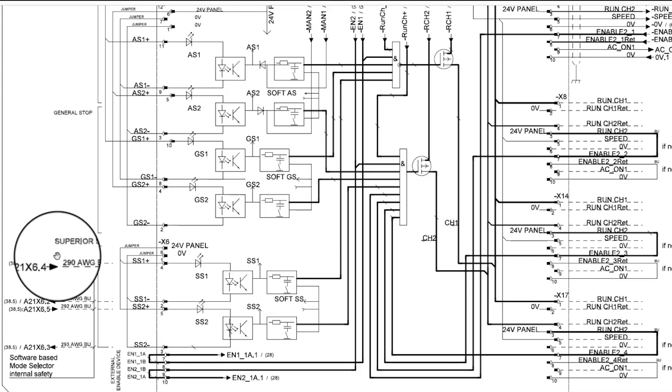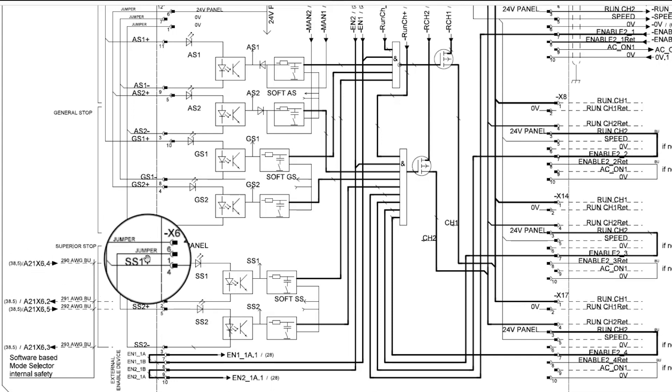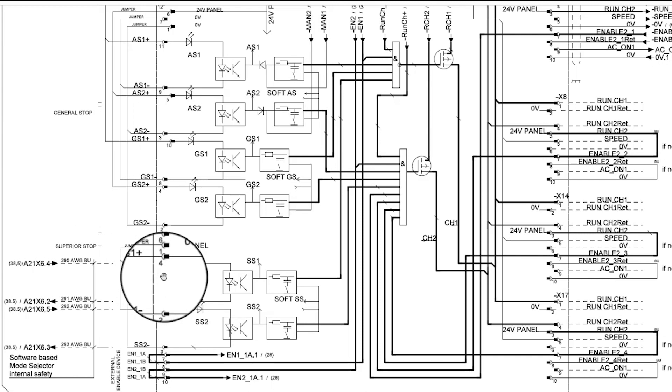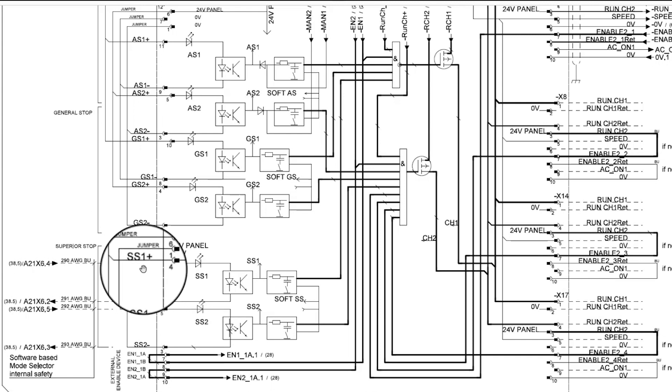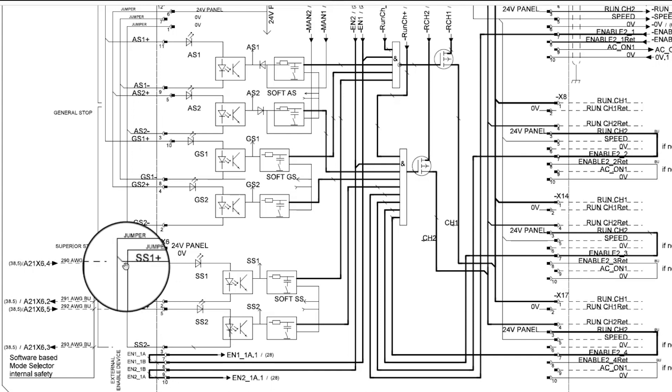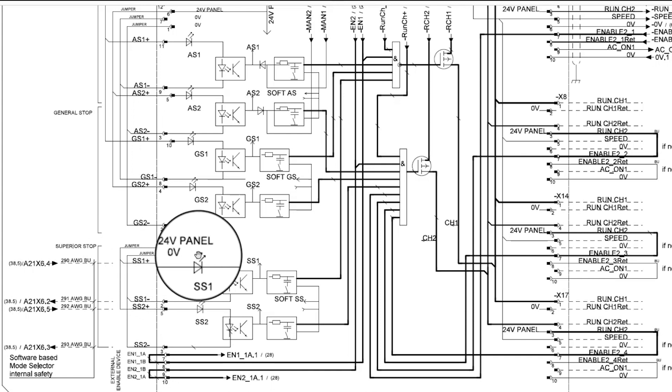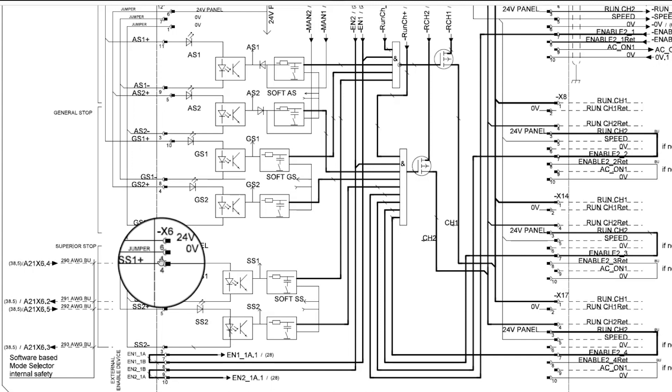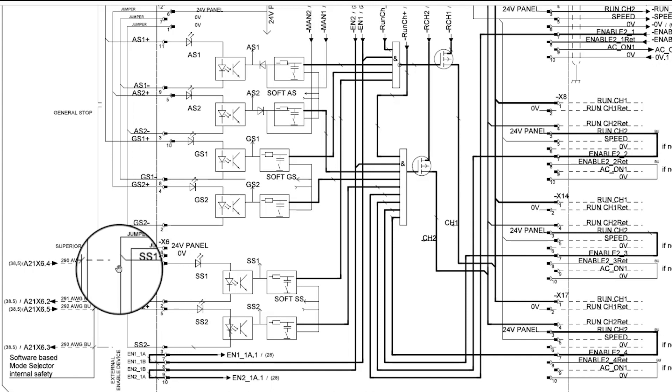The X6 connector in position 4 is the first positive chain for superior stop named SS1 positive. As you can see there is a 24 volt supply coming out of the panel board on connector X6 position 6 which is being pushed through the factory jumper to positions 4 and 5.